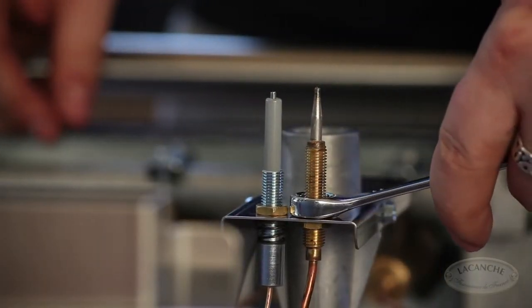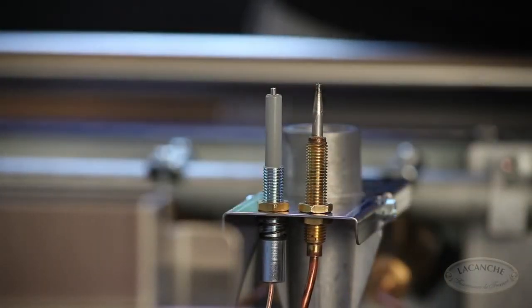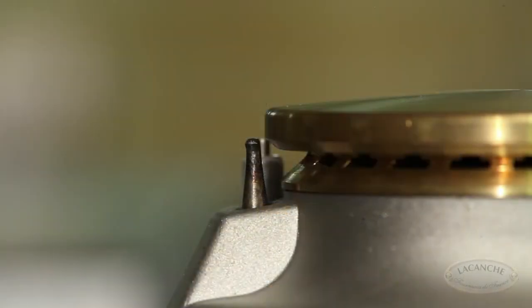Lock the probe into place by tightening the lock nut. Make sure that the tip of the probe is at the same height as the lower leading edge of the burner cap, shown here.